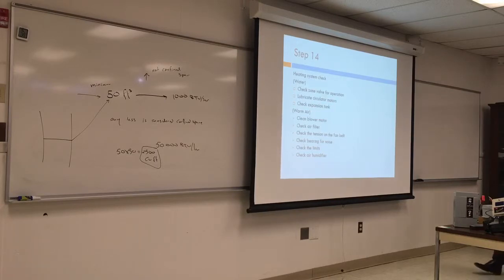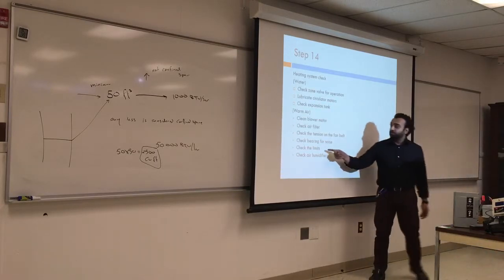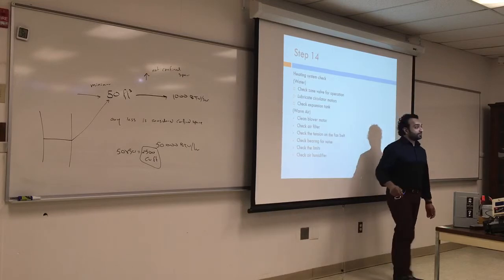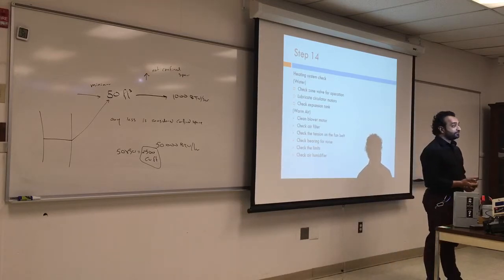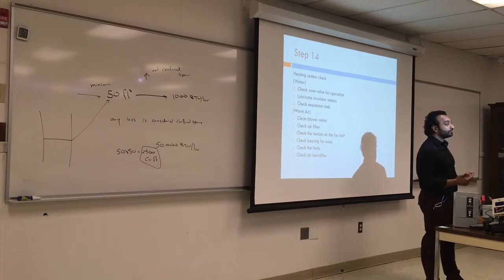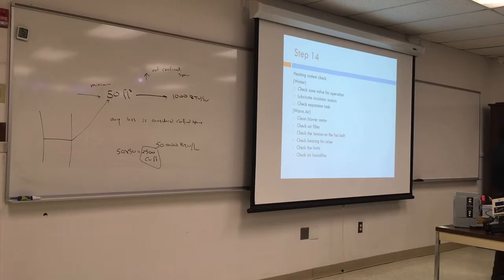Check the limits. This is very important. Checking the limits in all systems. Those limits are for a reason. If the system is turning on, those limits are supposed to turn it off and bring it on. So try to check the limits before you leave the site.